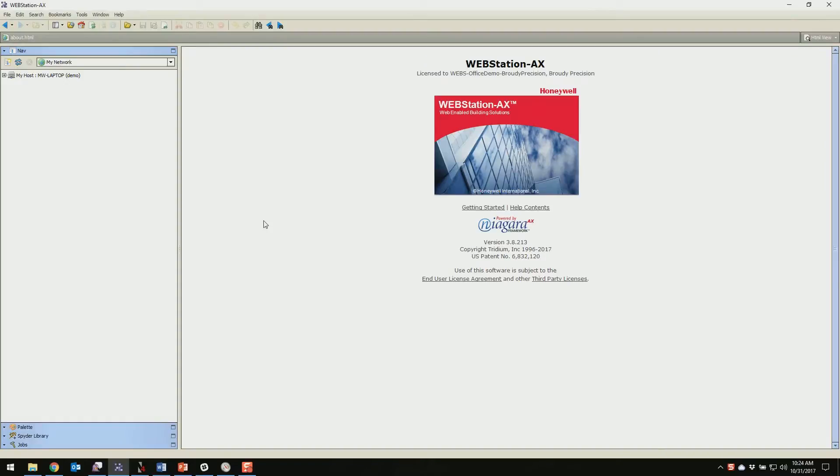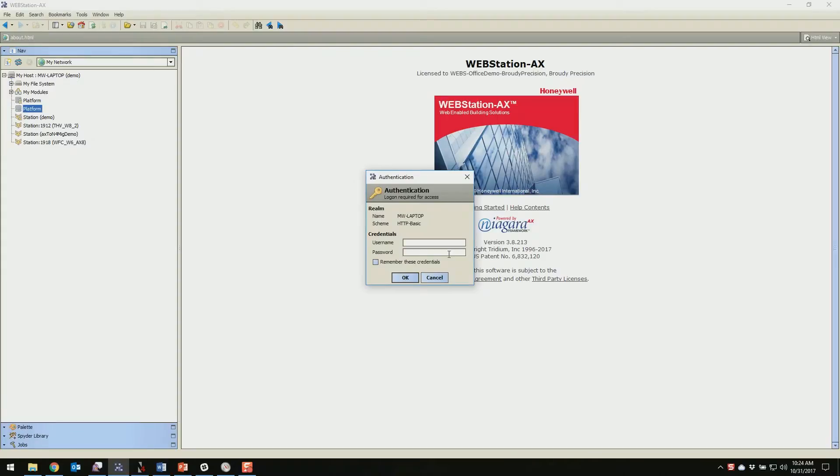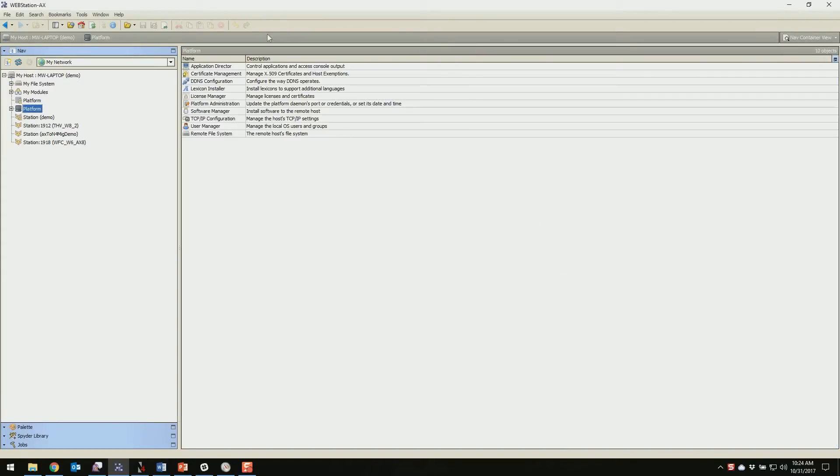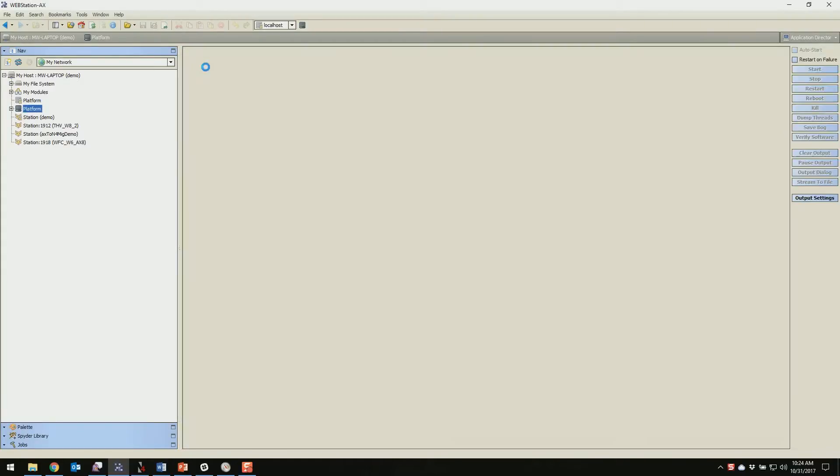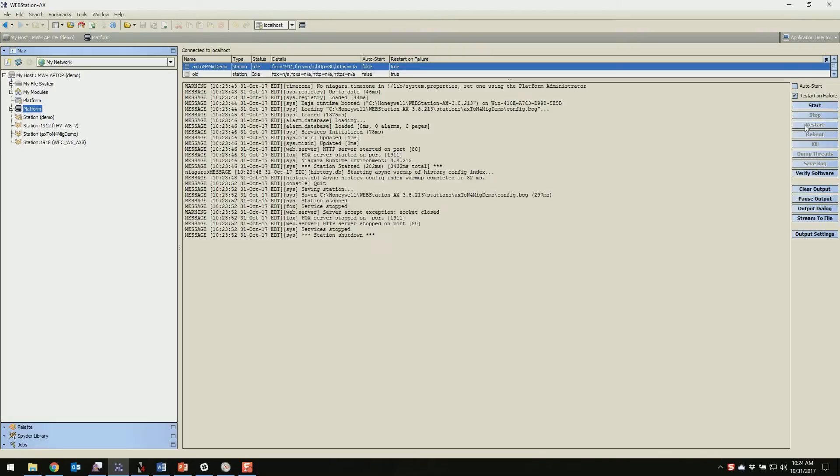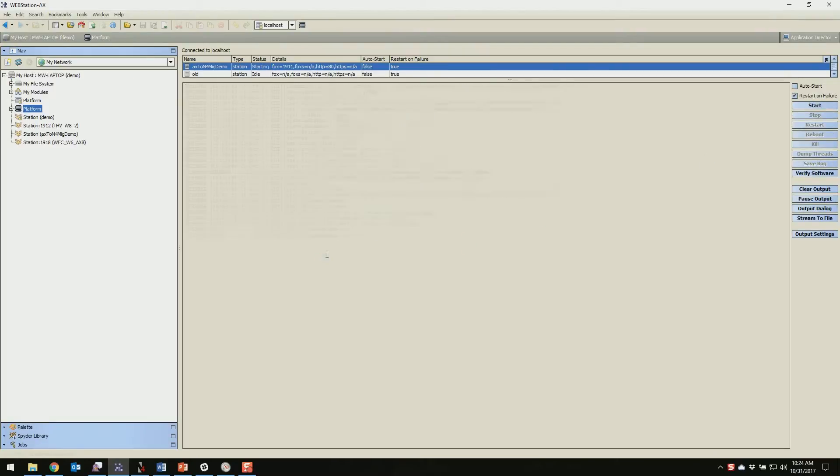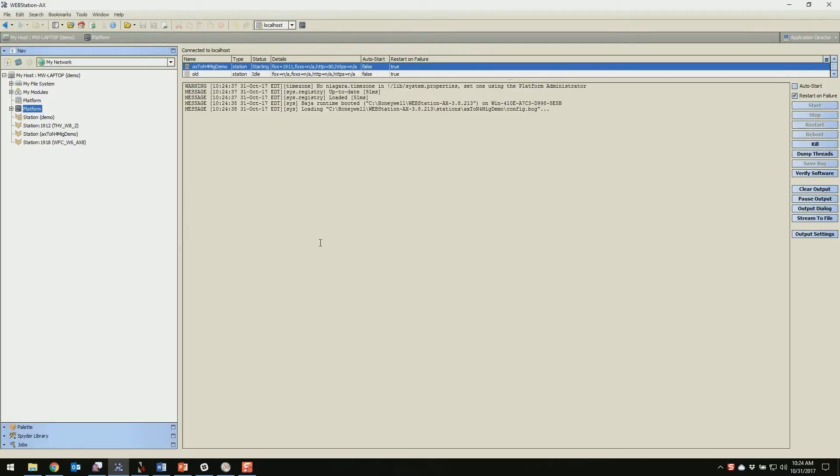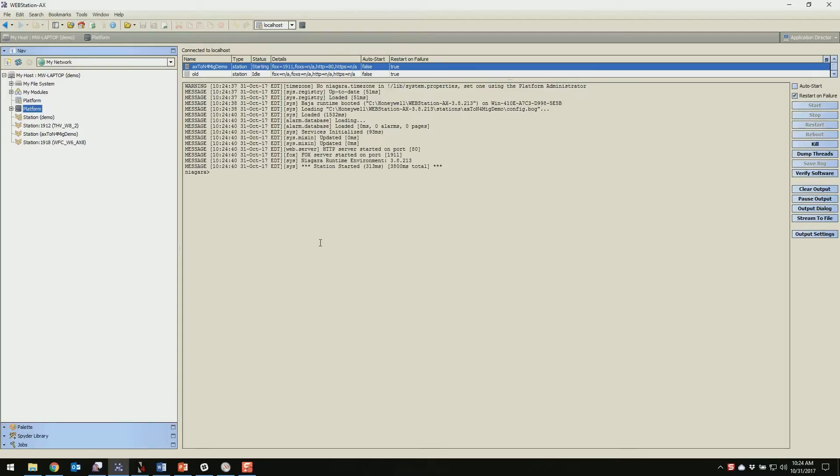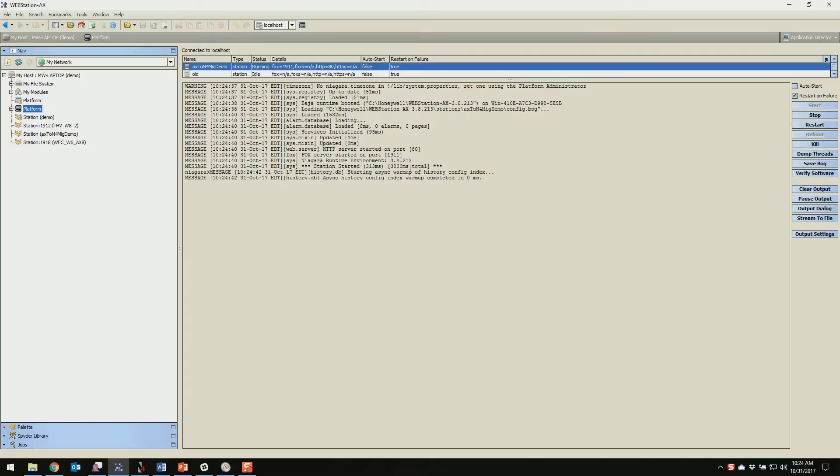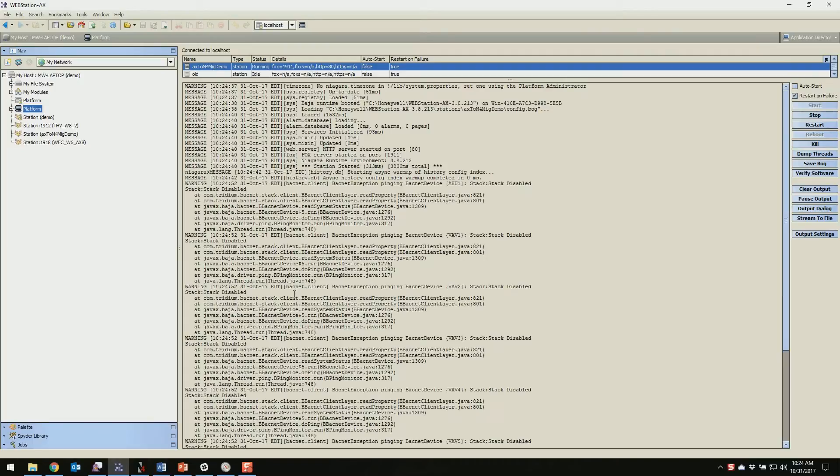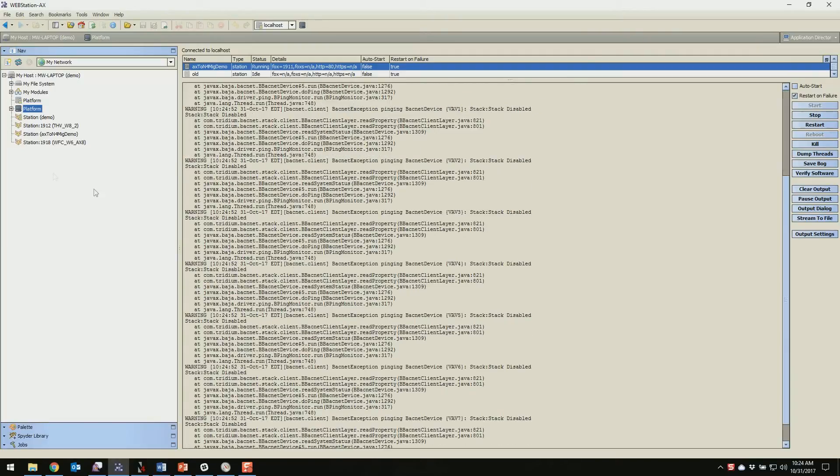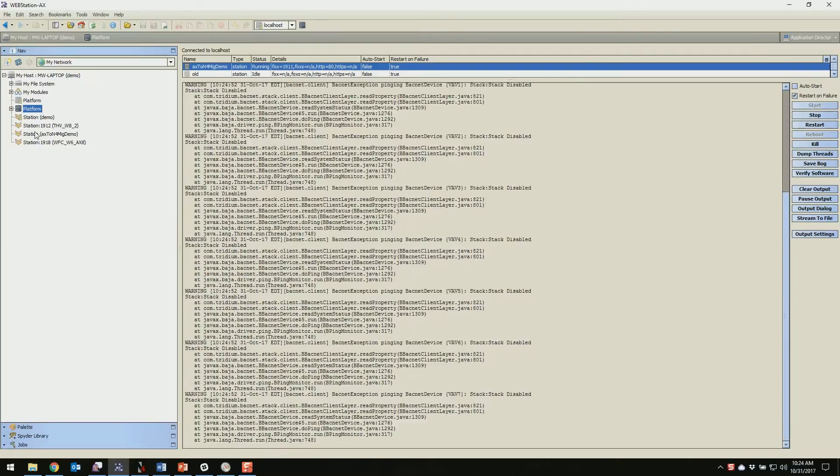All right, now we're in 3.8 and we're going to log into our local platform and open up our application director and start our station that we want to migrate. It's a good idea to just sit here while this starts up because you may be missing modules that you had in your Jace that you don't have on your machine. But we are good to go here. Station started. So we're going to log into the station now.